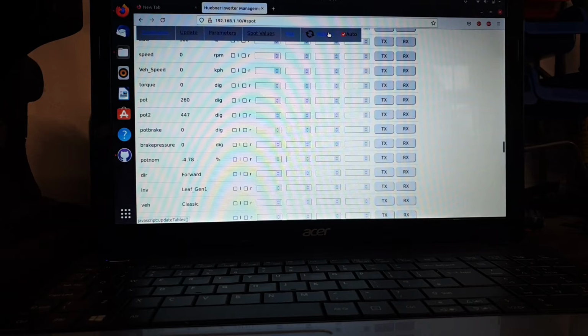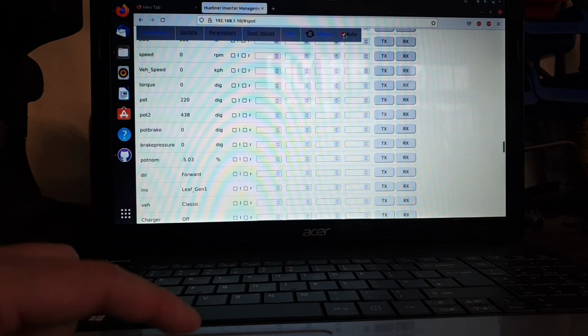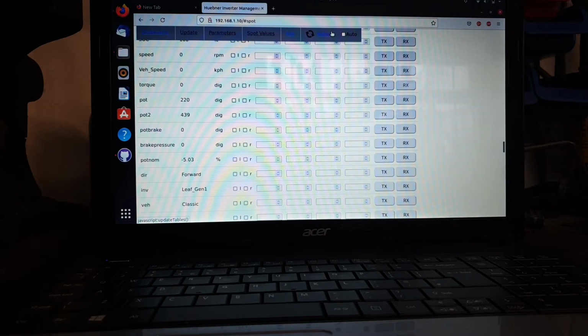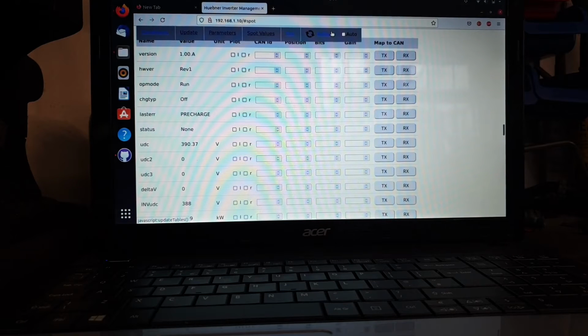Now we know this is because we've changed that UDC min value to a voltage above what we have available. UDC min is basically saying unless we have a minimum of 480 volts available, we will not allow positive torque. So let's go back and change that.